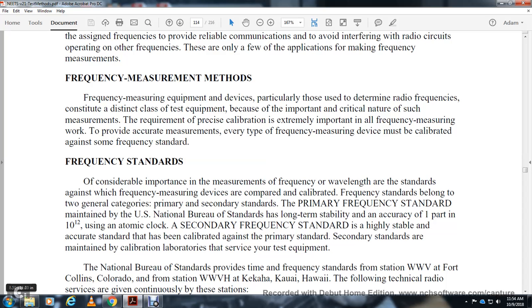The frequency standards belong to two general categories, primary and secondary standards. The primary frequency standard maintained by the U.S. National Bureau of Standards is for long-term stability, with an accuracy of 1 part in 10 to the 12. Usually, the atomic clock is the primary one. The secondary frequency standard has high stability, but the accurate standard has been calibrated against the primary standard, with secondary standards maintained by the calibration laboratory service for your test equipment.